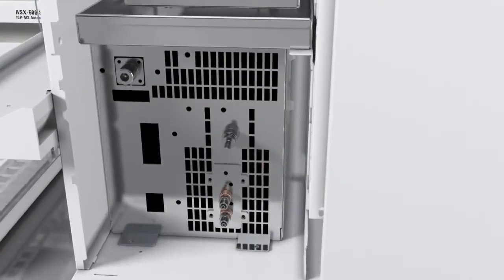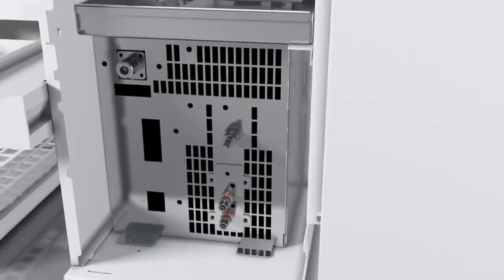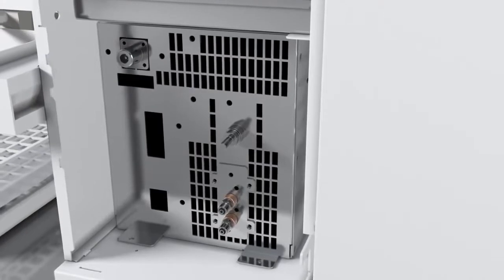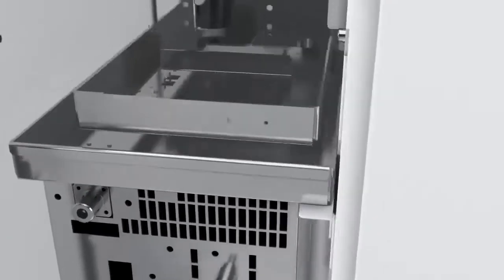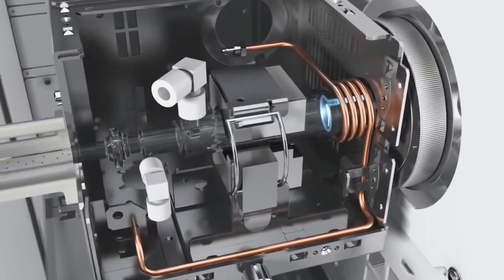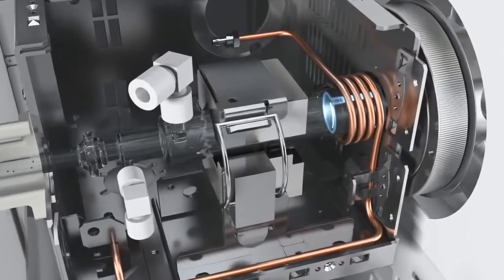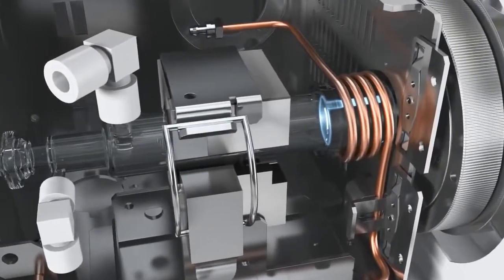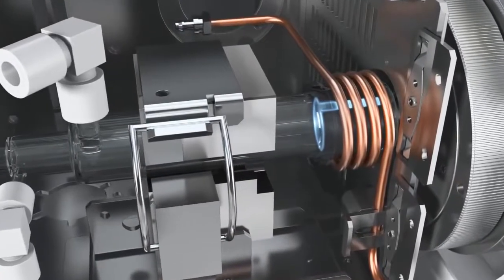This delivers the most effective matrix decomposition, lowest interferences and highest sensitivity, especially important for poorly ionized elements. The generator uses a computer-controlled frequency matching network to instantly adjust to changes in sample type, allowing volatile organic solvents to be measured with ease.